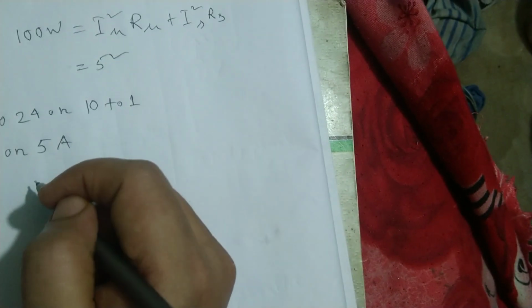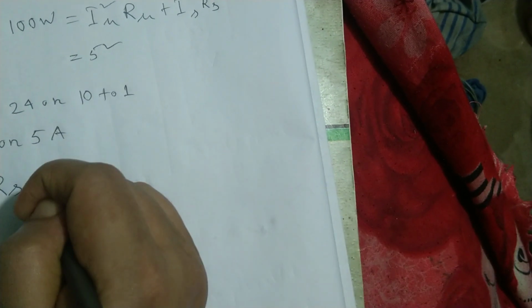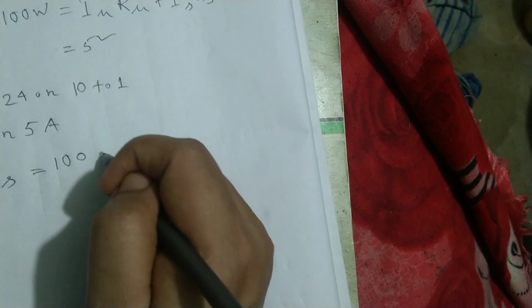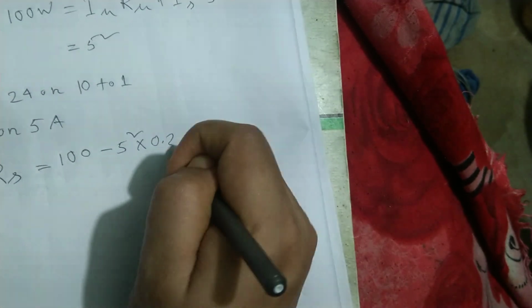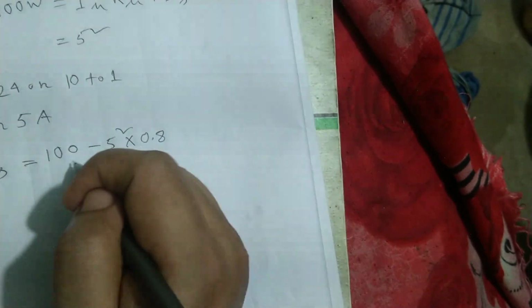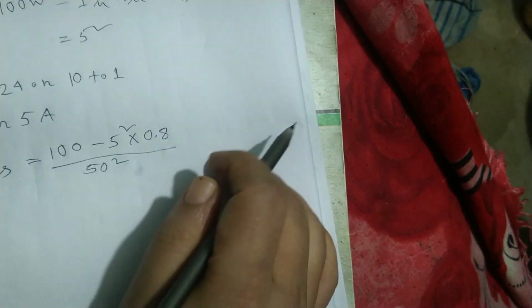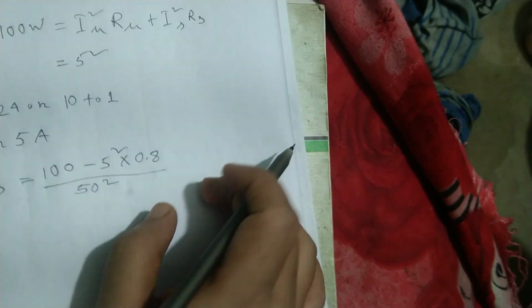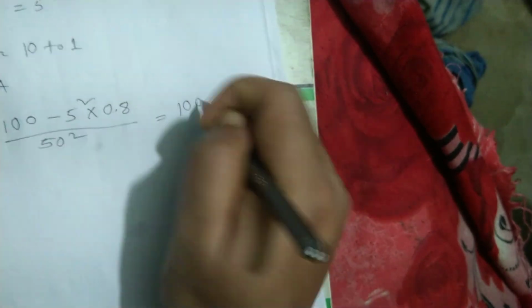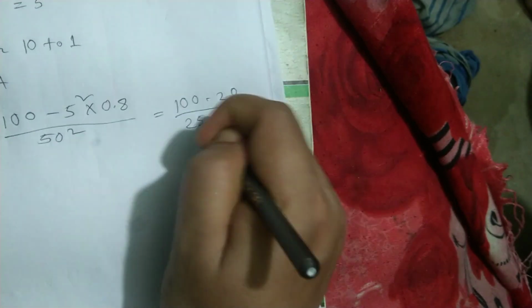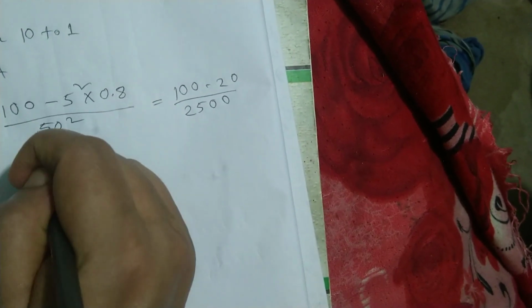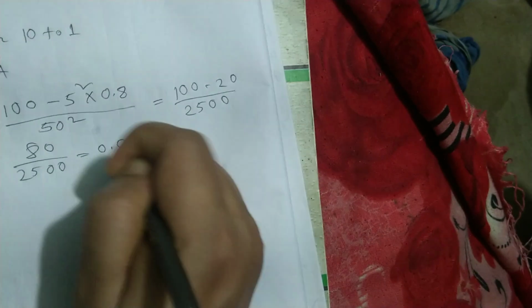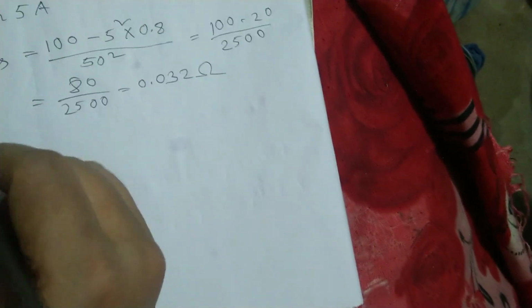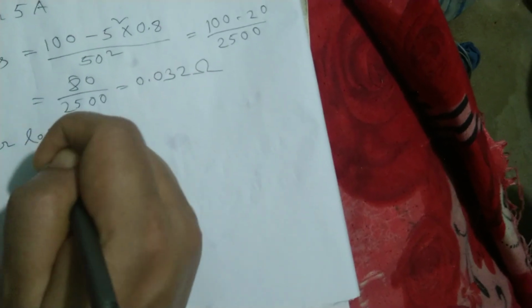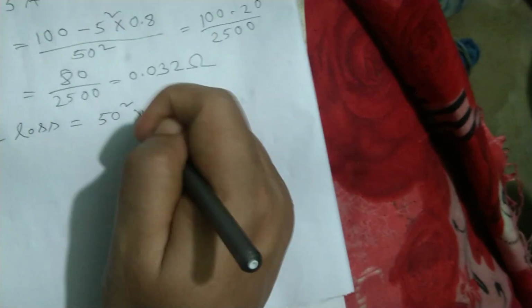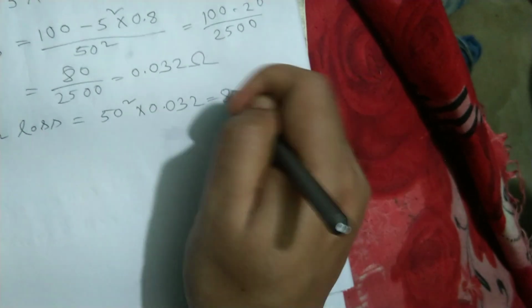Now I have to find out Rs. Rs equals 100 minus 5 squared into 0.8, divided by 50 whole squared. So what is the answer? 100 minus 20 divided by 2500 equals 80 by 2500, which equals 0.032 ohm. So the power loss is equal to 50 squared into 0.032, which is 80 watt.